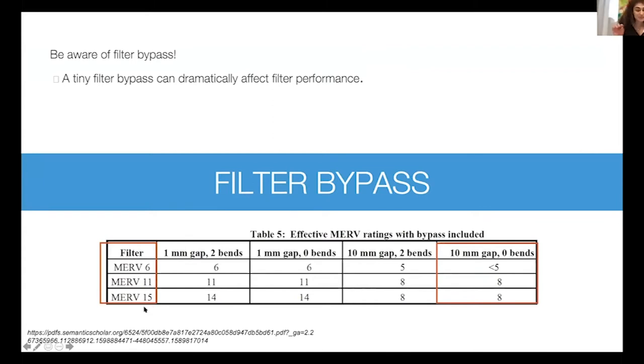And I put here a snapshot. I have the study in a link. Please take a look at it. But basically, if you have a MERV 15 and you have a 10 millimeter gap, so a 1 centimeter gap, a very, very small gap, a MERV 15 will act like a MERV 8. So imagine this: you paid for it, you put it in, it was probably a headache to put in. If you leave a very small gap, it's going to act like a MERV 8. So this is to say that it's important to take care of filter bypass.